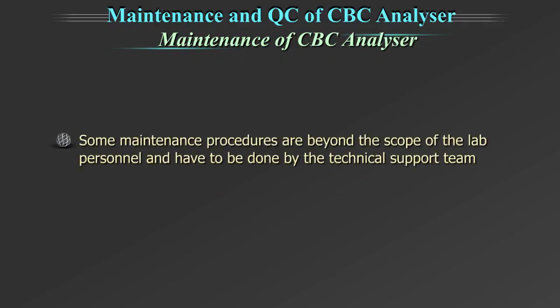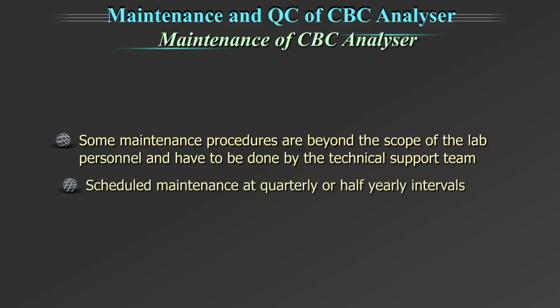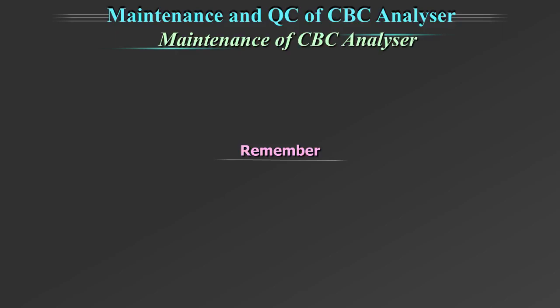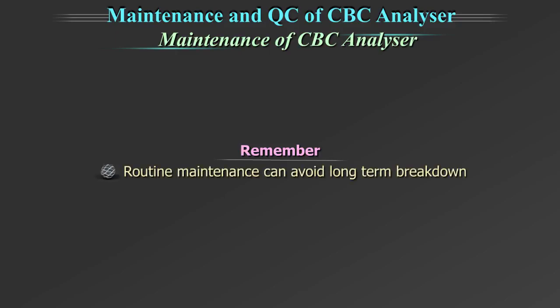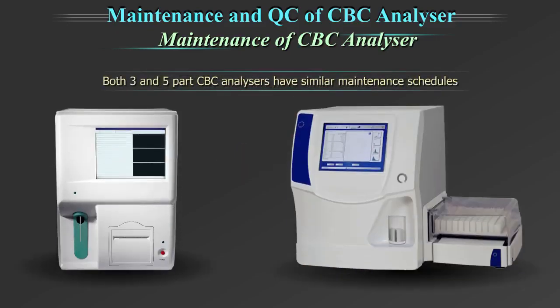Some maintenance procedures are beyond the scope of the lab personnel and have to be done by the technical support team of the manufacturer. These are scheduled maintenance at quarterly or half-yearly intervals, also called preventive maintenance. It is important to remember that routine maintenance can avoid long-term breakdown of the equipment. Both 3 and 5 part CBC analyzers have similar maintenance schedule as per manufacturer guidelines. Details of these need to be understood and followed regularly.